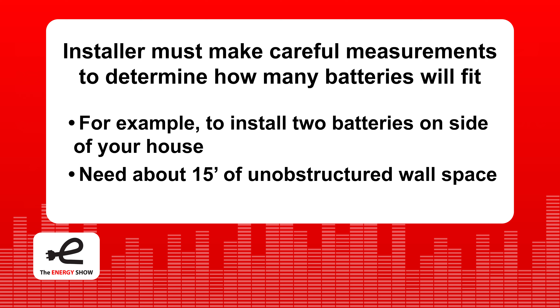These are things good installers will measure, and you want to make sure the installer doesn't lowball the price by ignoring battery spacing issues from windows, doors, gas meters, and property lines. Basically, the only way to really understand exactly where the battery is going to go is for the installer to physically go there with a tape measure and understand what the rules are.